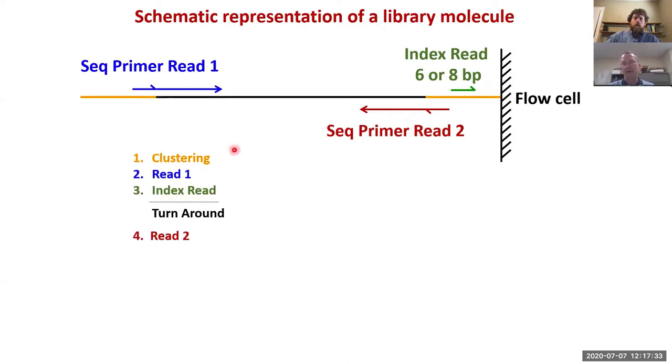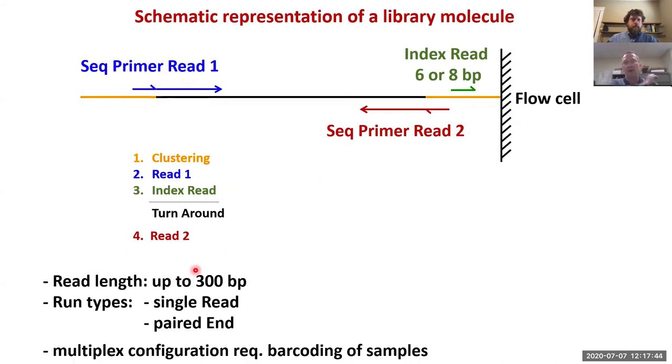The summary is here: first the clustering which is the immobilization and amplification of a molecule on the flow cell, read one, the index read, the turnaround, and then read two. With the NextSeq instrument which we have on campus you can sequence up to 300 base pairs and you can sequence either in single read mode or paired end read mode. You can choose the length of your read as long as it's 300 base pairs, so you could theoretically do 298 cycles in one direction and 10 in the other direction or whatever works for you.